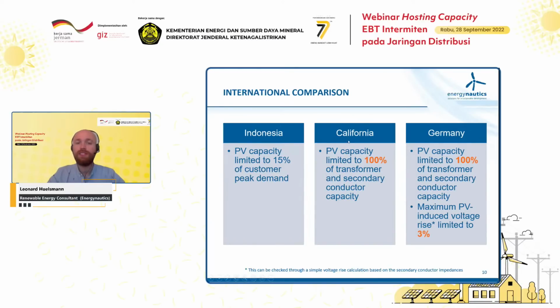However, in California, for example, the PV capacity is limited to 100% of transformer and secondary conductor capacity. So these are basically the low voltage lines. Here you see the direct difference from 15% to 100%. So basically the size of the transformer or of the conductors will be the limitation, and not anything like this. Same goes for Germany, with the exception that there's also a certain maximum voltage rise that is defined, which can be checked by simple calculations, and that also limits a little bit the amount of PV generation that can be added.